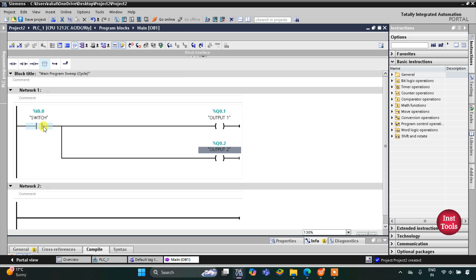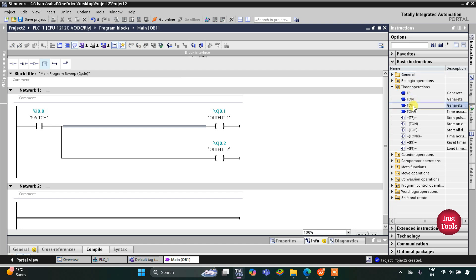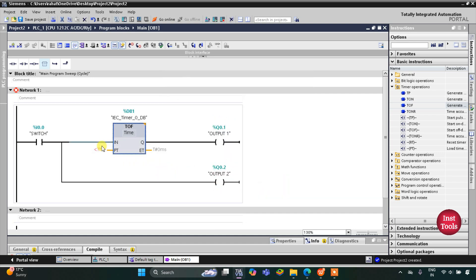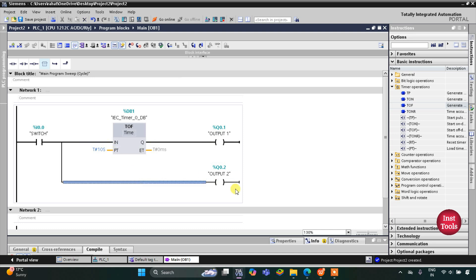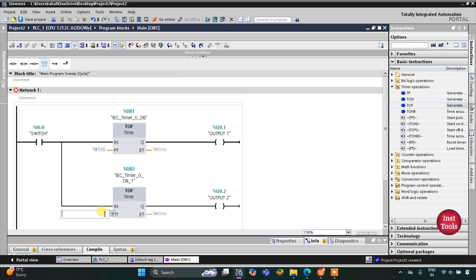When the switch is turned off, output 1 and output 2 would immediately turn off without a timer, but we need output 1 to turn off after 10 seconds and output 2 after 15 seconds. For that we use a T-OFF (off-delay timer) operation. The preset value for output 1's T-OFF is 10 seconds, and for output 2's T-OFF it is 15 seconds.